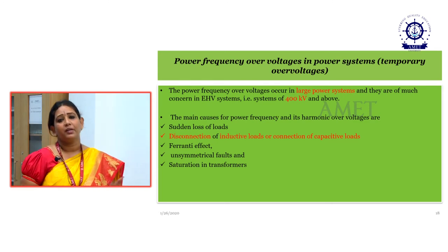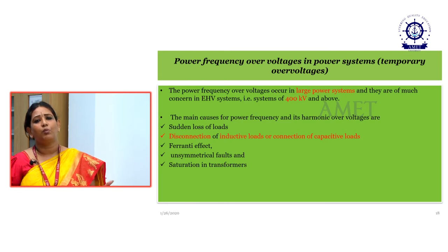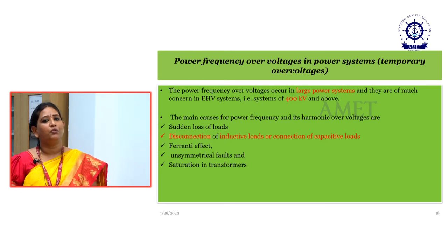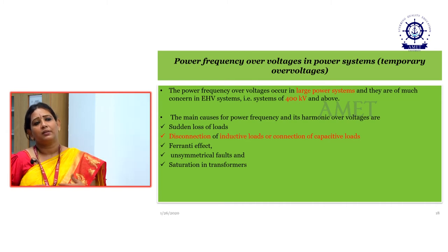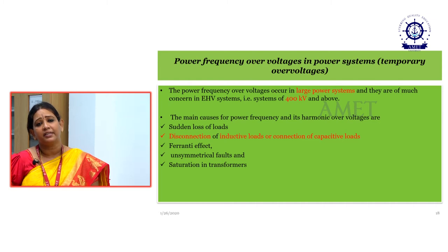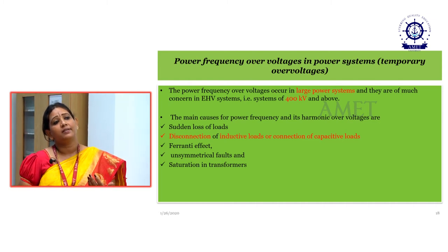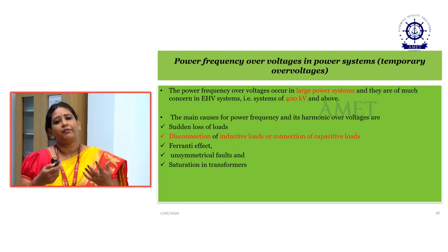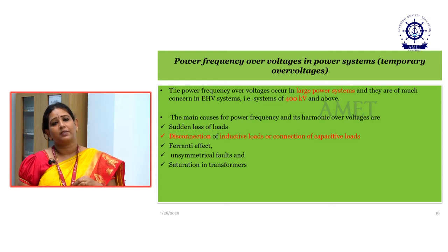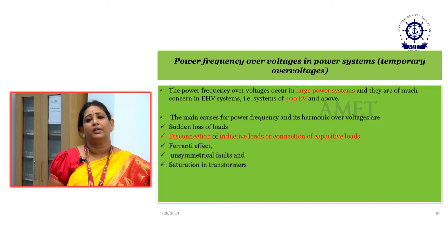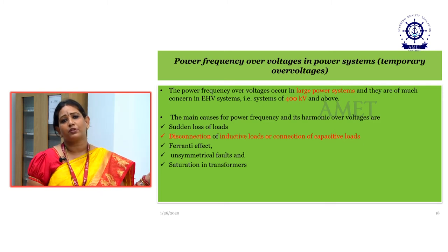And then saturation in transformers. Saturation in transformers is also a quite challenging task, because on the distribution side or the transmission side we go for transformers. If we elevate the input voltage more than the rated value, the transformer's exciting current starts increasing, and once it reaches a maximum value it undergoes saturation. Very high order harmonics are also injected into the system. So saturation in transformers also has to be taken care of.